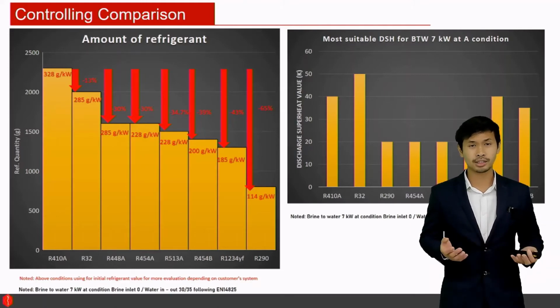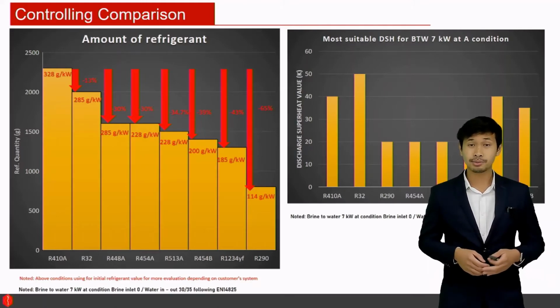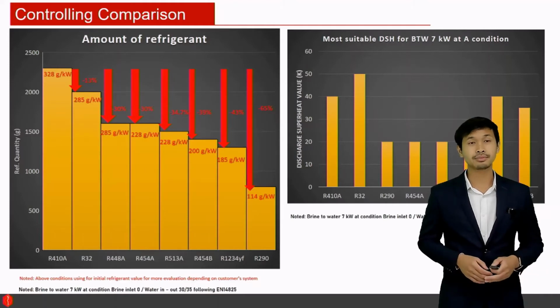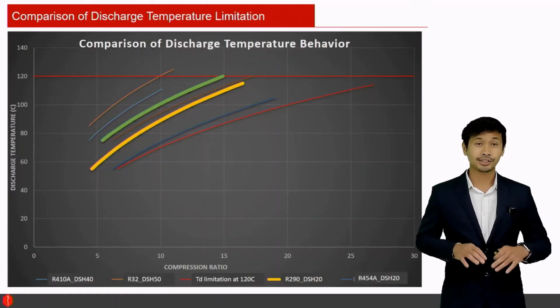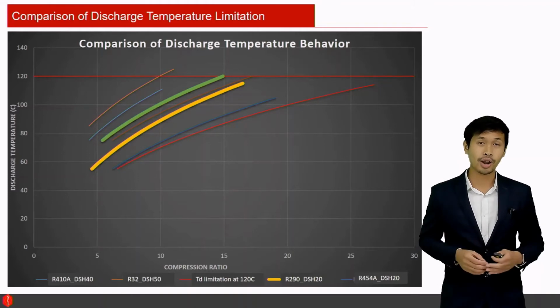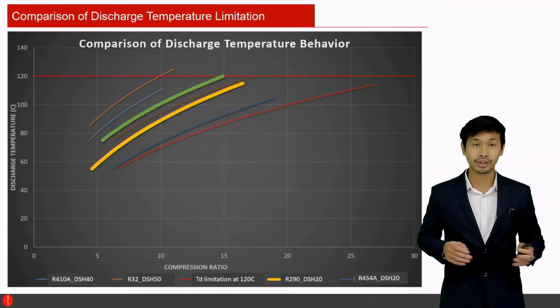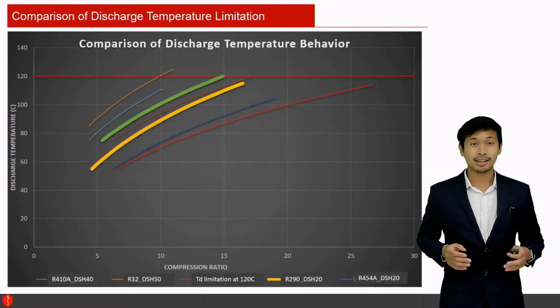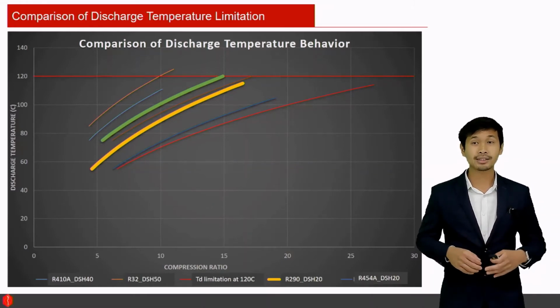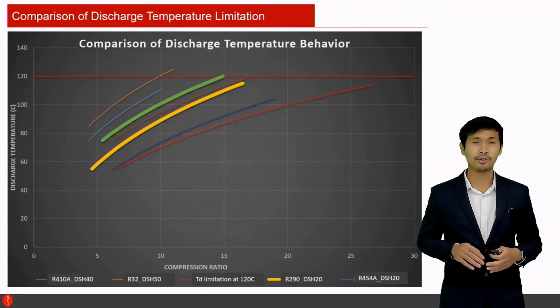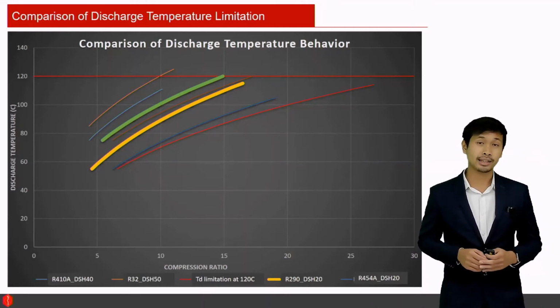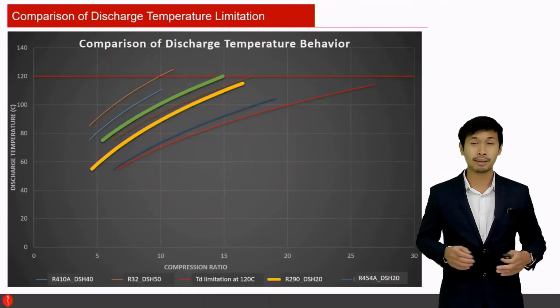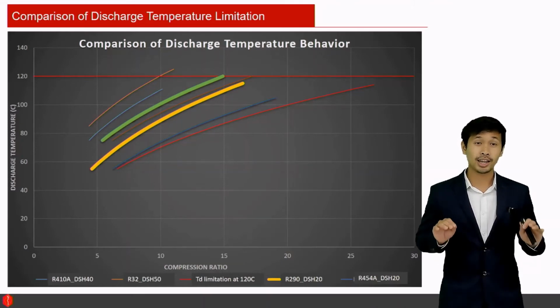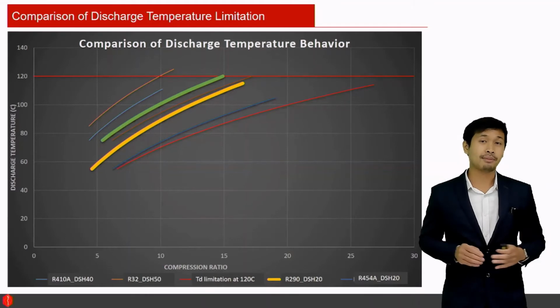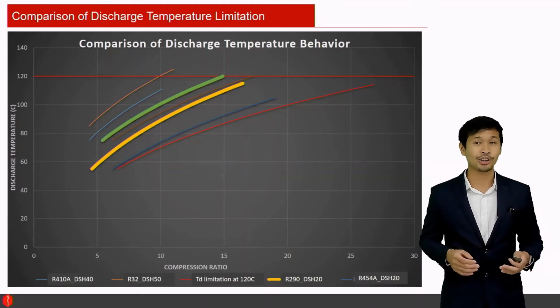And what about the other concerning point? Let me clarify them in the next slide. So, I studied more about that in other compression ratios to see discharge temperature behavior. The conclusion is that it's not a big issue at all, even about the discharge temperature issue. To use other refrigerants like R290, R454B, even the compressor overlay in the high compression zone for heat pump application, there is no need for special cooling equipment for safety matters such as liquid injection or economizer control.